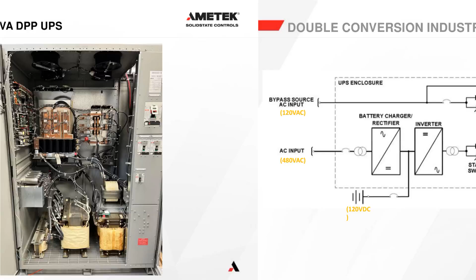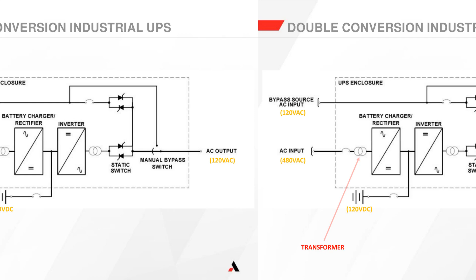Here is a single line diagram of our UPS systems. We have our 480 volt three-phase input into the rectifier. The rectifier converts AC into DC, and the inverter converts DC back into AC. Our static switch is how we choose between the inverter output or the bypass input to go to our load circuits. I'll explain these components in more depth as we go through the presentation.